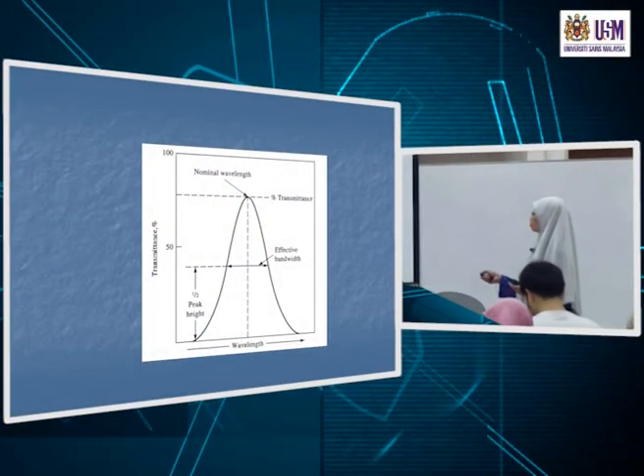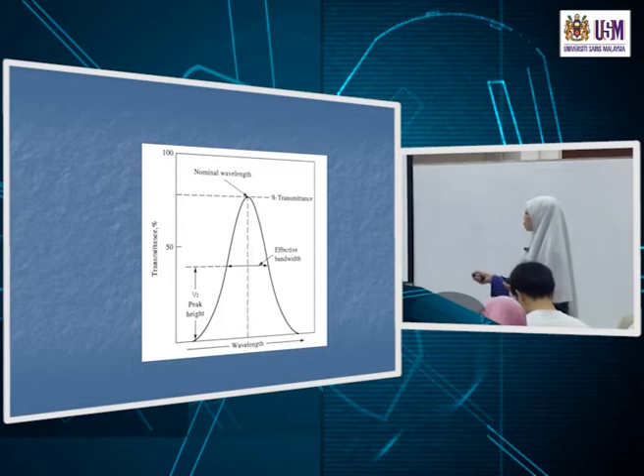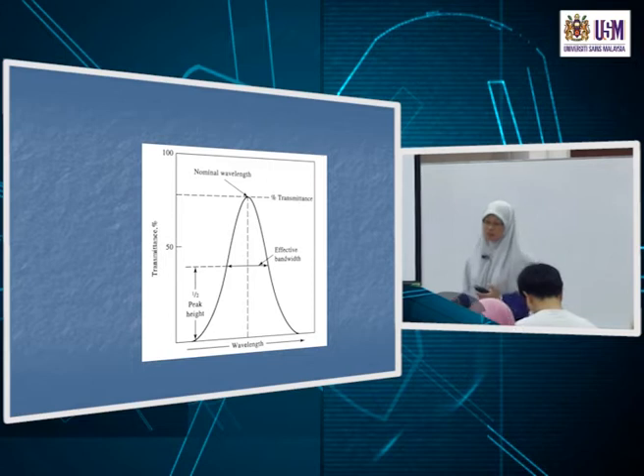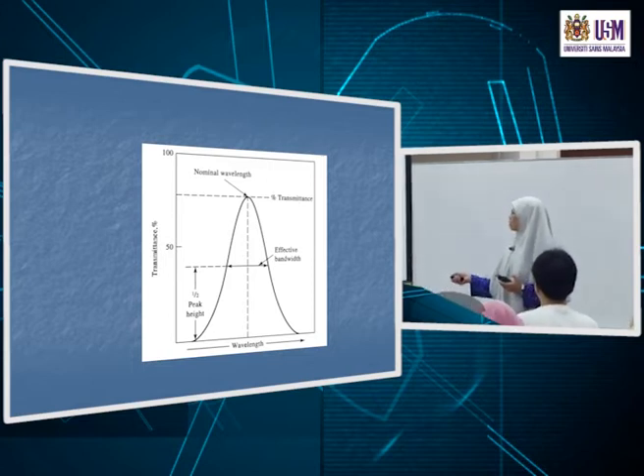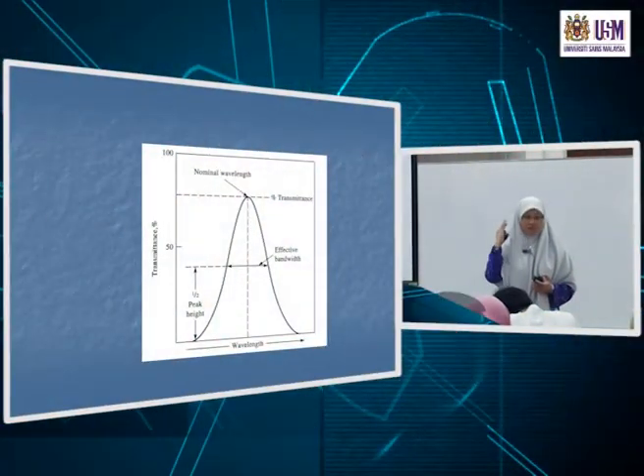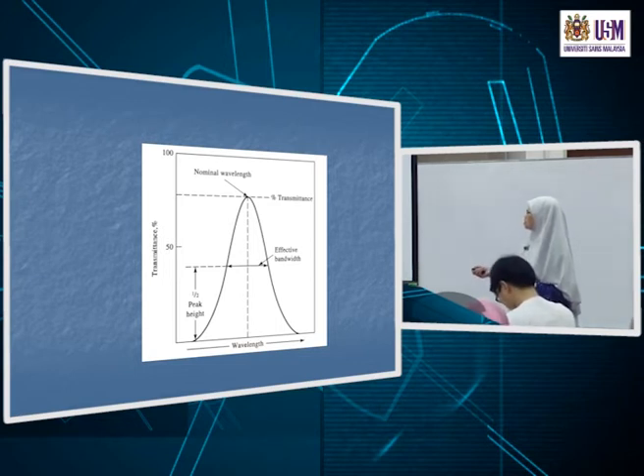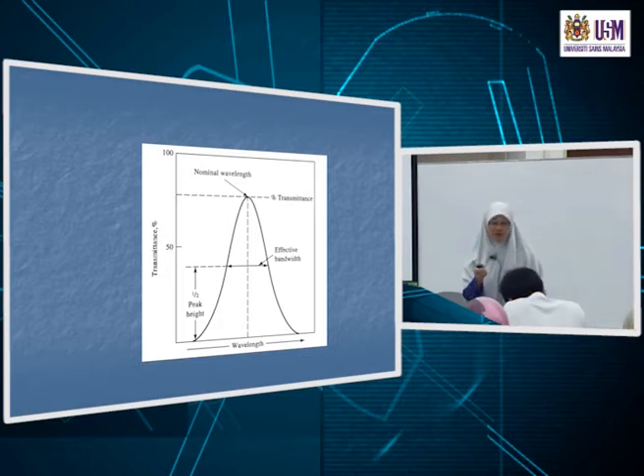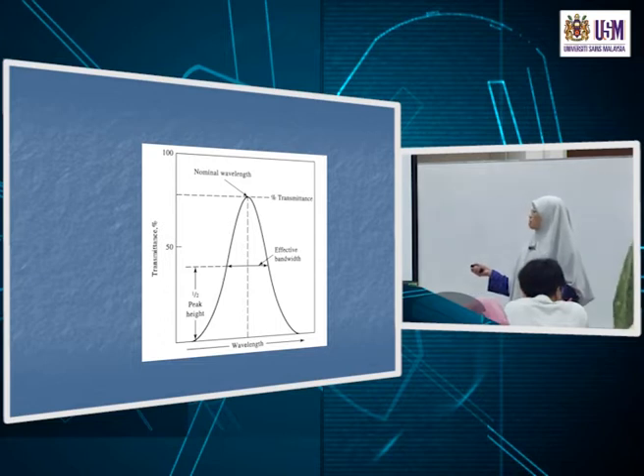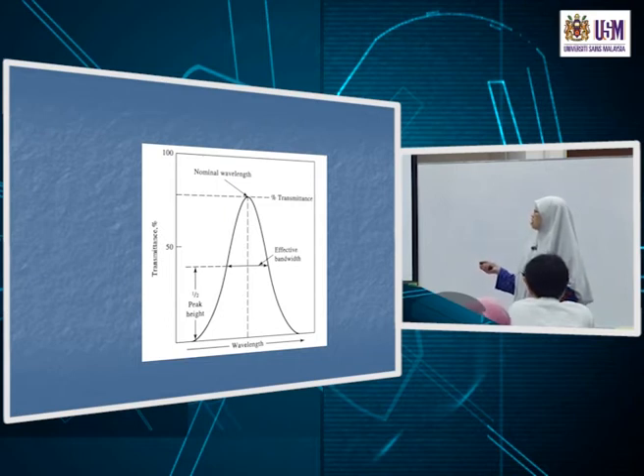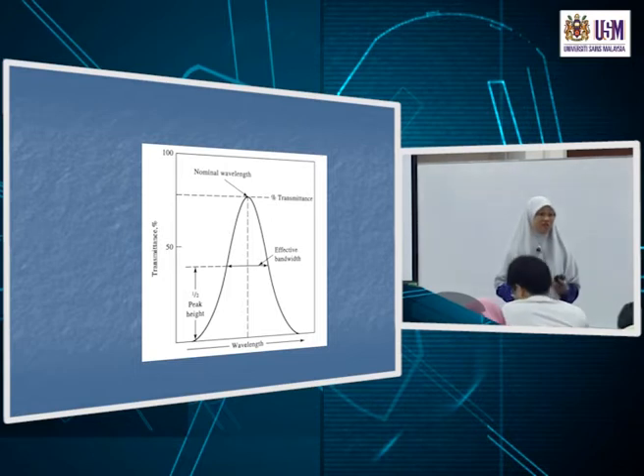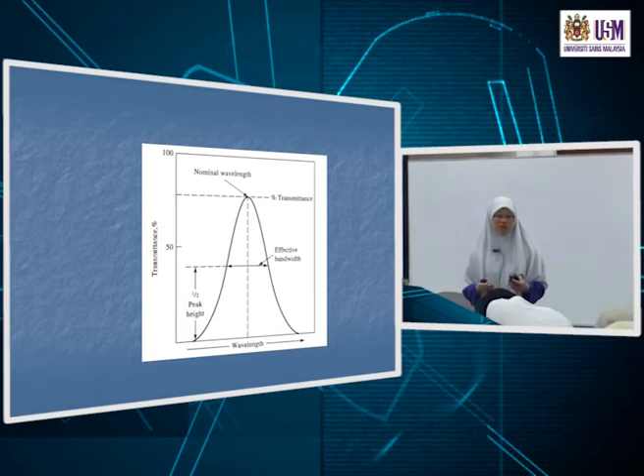How do we look at the spectral bandwidth? We look at the effective bandwidth — the range of wavelengths at half the maximum peak height. You never get a single wavelength coming out. That is the ideal situation, but it does not happen in real life. You get maximum transmittance at the chosen wavelength, but you also get a range of wavelengths.